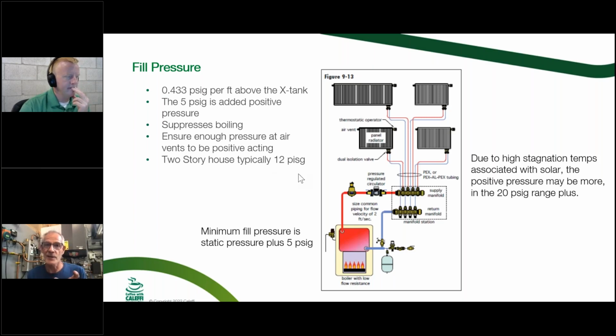And know that the tank might say pre-charged to 12 or 15 on some of them. I wouldn't bet the farm on that. Just because somebody put that in at the factory doesn't mean when it gets to you, it still has that exact number. So get an accurate gauge, like a bicycle or an ATV gauge, a low pressure gauge that you can get a good accurate reading on, especially if you're looking for a 1 to 2 pound range. You don't want to put a 100 PSI pencil gauge on it and have it say, yeah, either 10 or 20. It doesn't get you an accurate enough number.